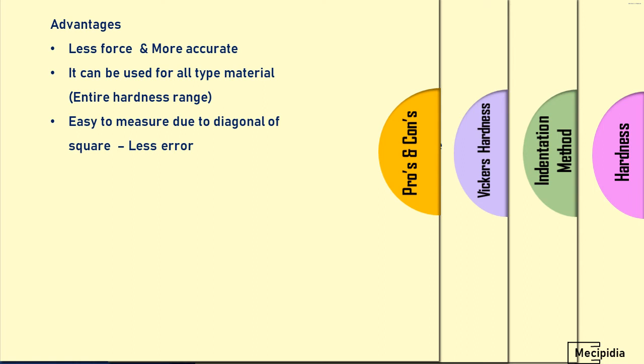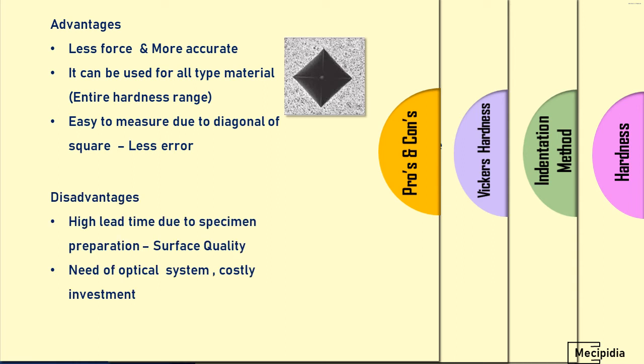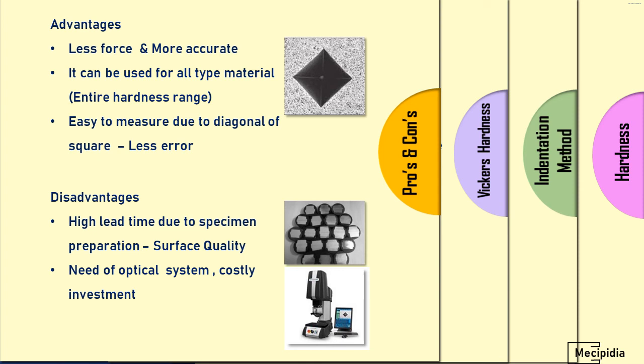Coming to the disadvantages: first, high lead time — because in Vickers hardness the indenter is very small, the specimen needs to be carefully prepared and only then can it be measured. So there is high lead time to prepare the specimen and ensure surface quality. Second, an optical system is required to measure the indentation accurately since it is very small and cannot be measured by the naked eye accurately. This requires a costly optical system, which is a significant investment.